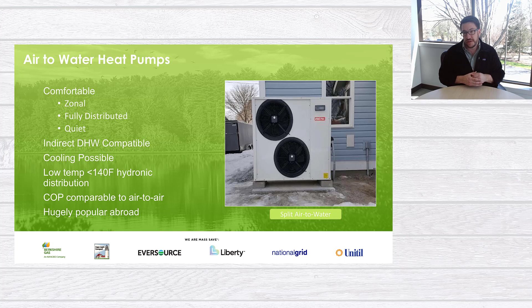With air-to-water heat pumps, cooling is also possible. The big issue right now, and why this is new to our market and not widely adopted, is it is heating the water up to around 120 to 140 degrees max. Most of our hydronic distribution system is looking for water that's like 180 degrees. So with air-to-water heat pump technology, it's proven, it's mature, but for a lot of homes, the distribution system as is may be incompatible with this type of heat pump without some sort of retrofitting of the plumbing distribution system.